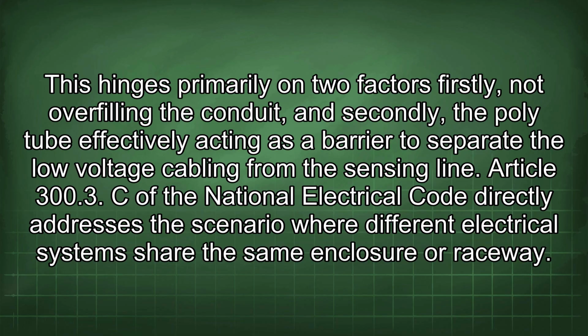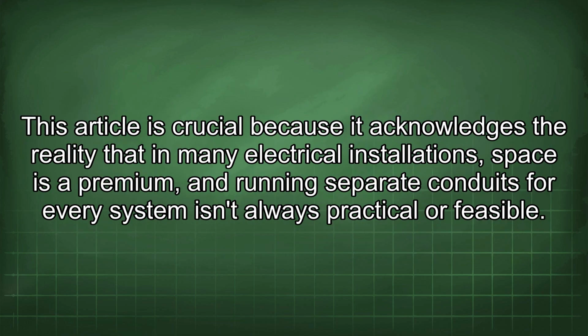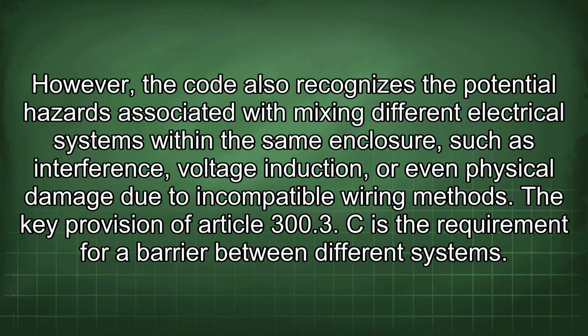Article 300.3(C) of the National Electrical Code directly addresses the scenario where different electrical systems share the same enclosure or raceway. This article is crucial because it acknowledges the reality that in many electrical installations, space is at a premium, and running separate conduits for every system isn't always practical or feasible. However, the code also recognizes the potential hazards associated with mixing different electrical systems within the same enclosure, such as interference, voltage induction, or even physical damage due to incompatible wiring methods.